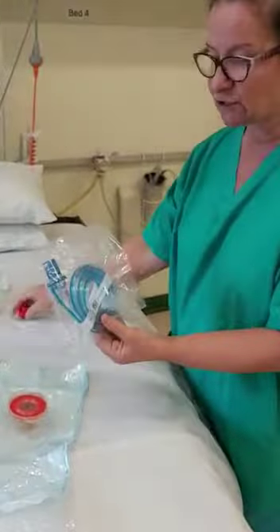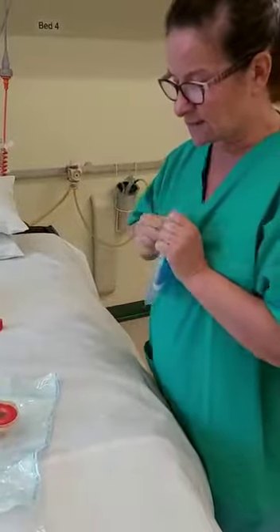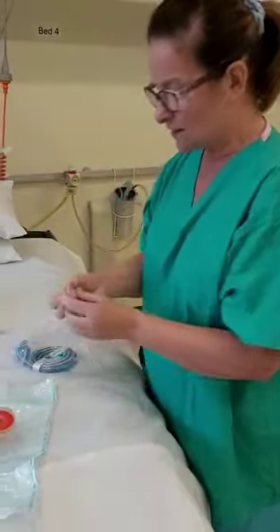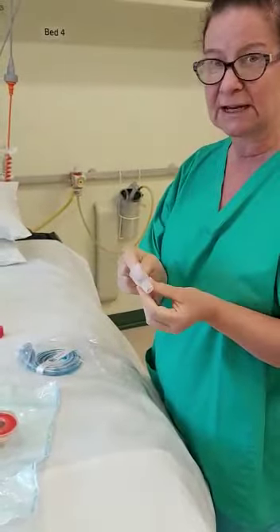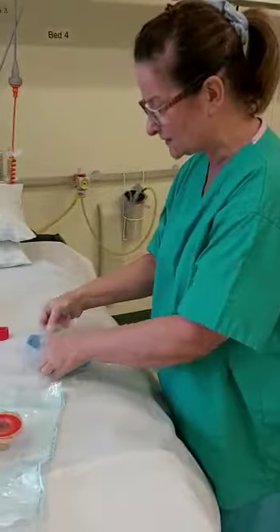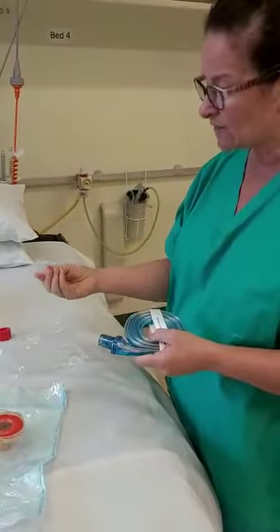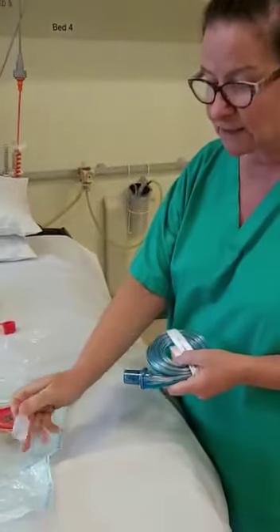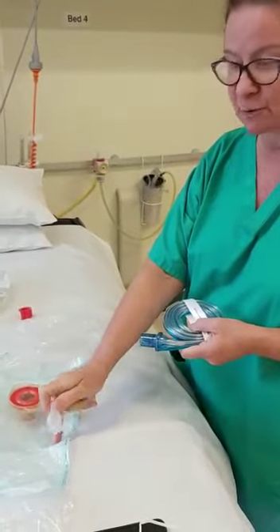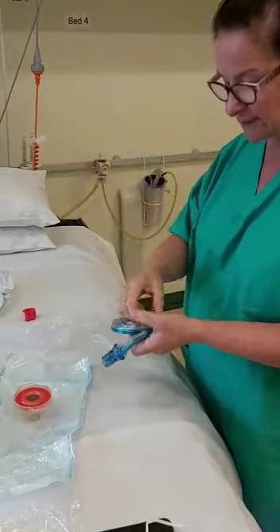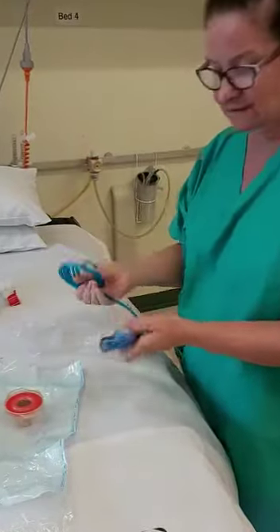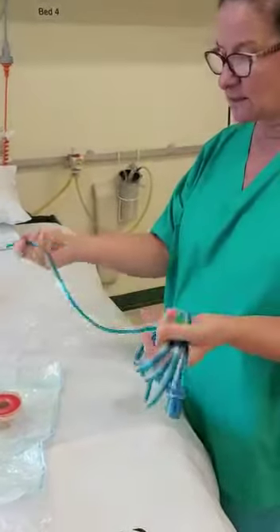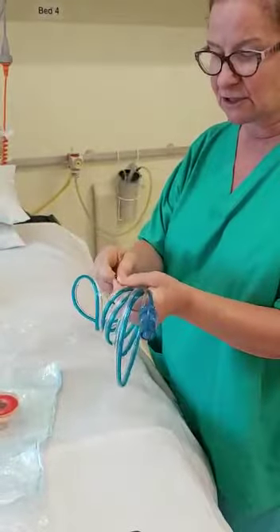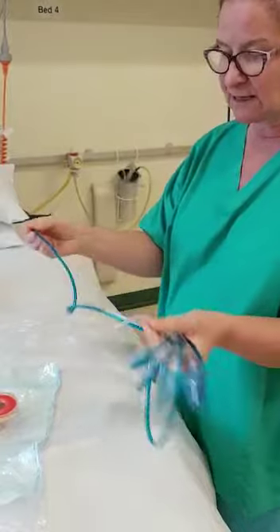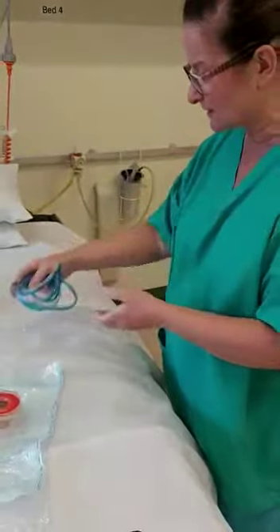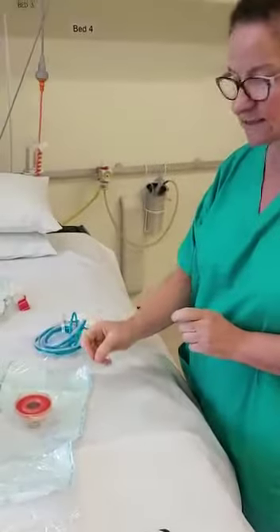And the other thing that you're going to need is your flow sensor tubing. So this comes in a packet with a little white plastic adapter, which you need to be used as part of your calibration process, so don't throw that away. And again, even once you've calibrated the ventilator, it can go inside the packet that the expiratory valve came from, so that it's there should you need it again. So take your flow sensor tubing out of the packet, and both parts are attached, blue and white tubing, so just pull that apart slightly. It'll just make it easier in a minute for us to attach that to the ventilator. So they're your parts that you're going to need.